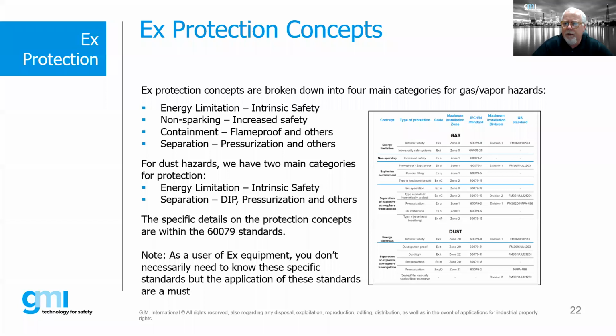So we'll talk a little bit more about the protection concepts. There are a bunch of different protection concepts that we follow in the international community. They're referenced by specific 60079 standards, and they are suitable for different gas zones, if you will. So intrinsic safety, EXIA, is a two-fault condition product, meaning that it can fail and it has redundancy and it is suitable for zone 0 environments.